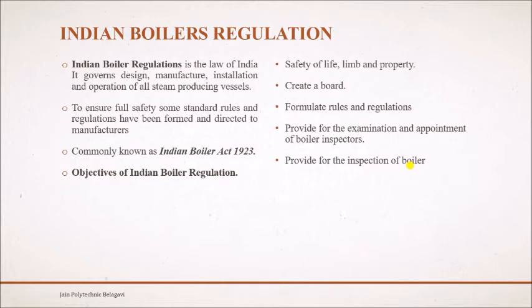So whatever the period of time is there, that will be set by the Indian Boiler Regulation. Here the inspector will check various things: the hydraulic test, steam test, and annual inspection. He'll go through various tests, and based on that he'll be issuing a certificate.